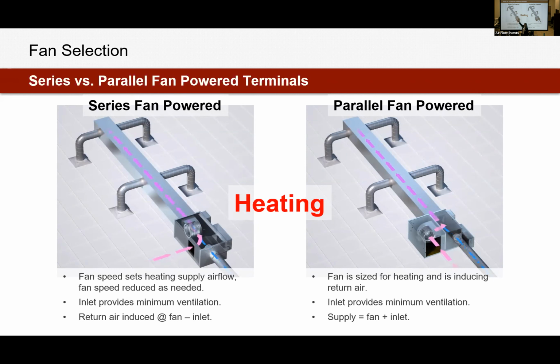So in my earlier example, our fan was running at 1,000 CFM. This valve probably dropped to about 200 CFM. The rest of that air now, 800 CFM, is what's getting pulled in through the return. So usually your fan is always staying at the same CFM. We're just changing the ratio of fresh air to return air.